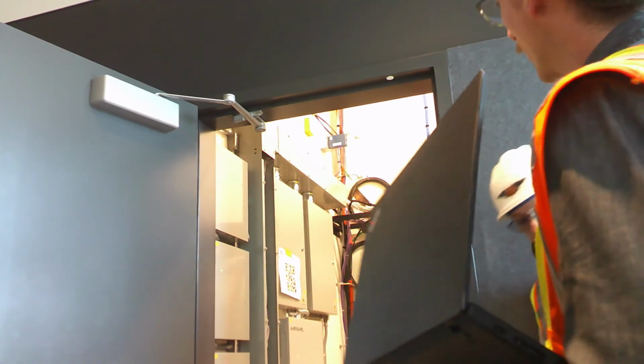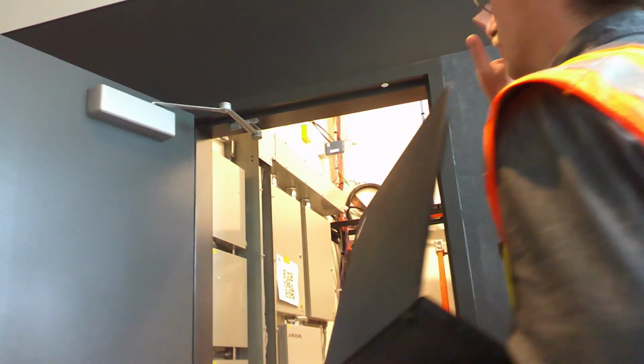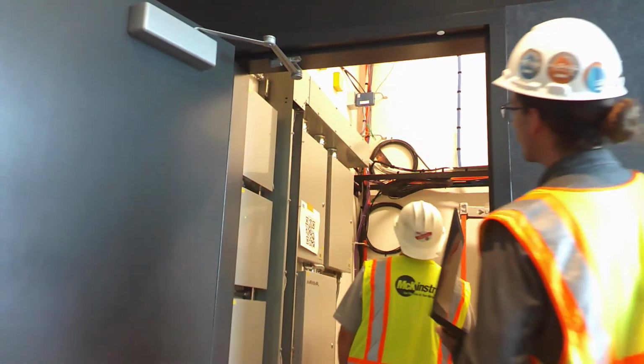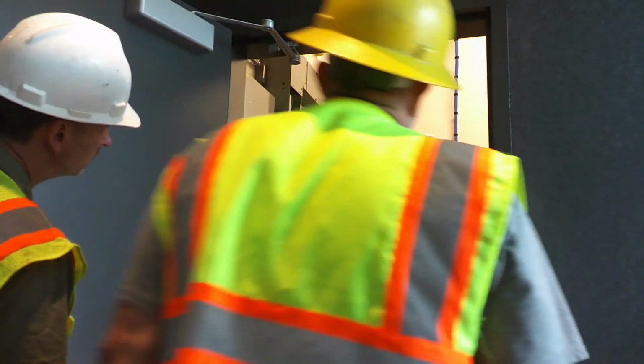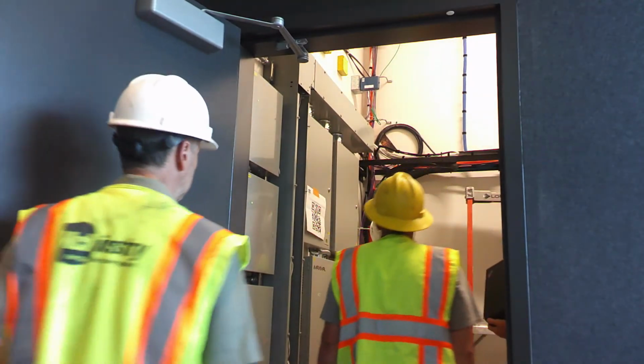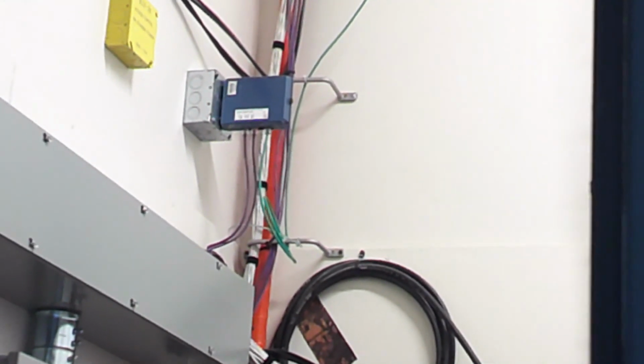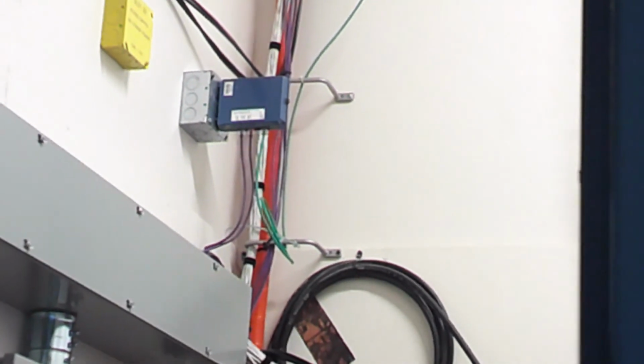And I don't know, you can take a look and probably see those LEDs all working how I described earlier. Oh, yep, you got some red, some blue, some greens. The blue flashing, green is telling you the network's going through, and then the red that's kind of buried on the right, right next to the blue one, that's telling you that it's talking to the room controller.